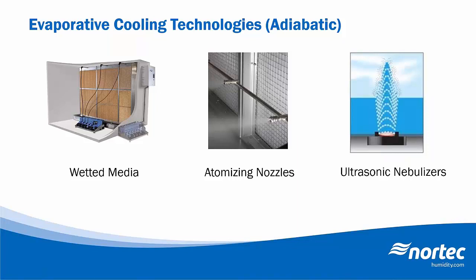So now let's take a look at the different adiabatic technologies that are available today. There are three main types of evaporative cooling or adiabatic systems. The first is a wetted media system. This is a system that probably everyone has heard about. If you've heard the term swamp cooler before, it's effectively the same thing. This type of system uses a wetted media pad placed directly into the airstream. As air passes through the pad, water is evaporated.